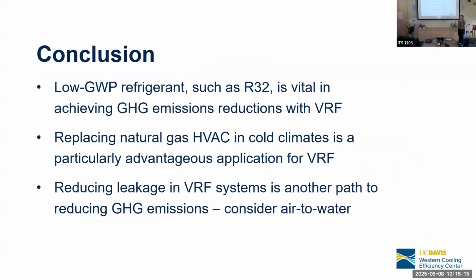So in conclusion, a low GWP refrigerant like R32 is essential for VRF systems if those are going to be a success. Particularly in colder climates, those are a good application. And if we can address the leakage in these systems, that could help a lot. One pathway is air to water systems, where you have a water loop, a hydronic loop, going into the building instead of refrigerant, that could potentially lead to less emissions.